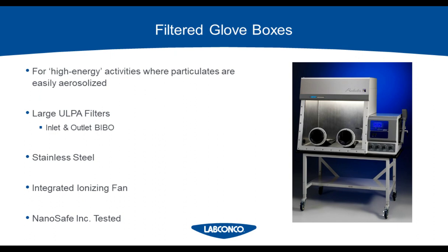So it's really reserved for opportunities in your laboratory or working environment where you have so-called high energy procedures, which are where you're moving or mixing or generating a lot more aerosols than you might typically be carrying out in a smaller open hood. This extra barrier of being completely sealed simply ensures that even if you were to spill something or create an unwanted level of nanomaterials, they're going to remain inside that glove box no matter what happens.